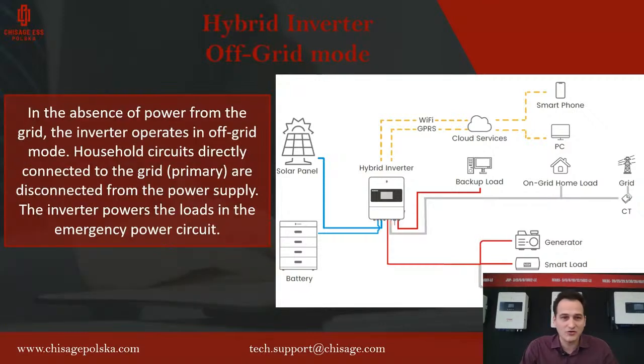And if we go to off-grid mode, of course, we don't have grid, so we cannot support the on-grid home load. That load is off. We have the backup load, of course, and we have the smart load, and we can have the genset. So the genset can work and charge the battery, can support the backup load, and the battery supports the backup load, and the system looks like this. So in less than 5 milliseconds, we are working this way. Again, when the grid comes back, the inverter will try to connect to the grid and automatically start working with the grid and support this on-grid home load.